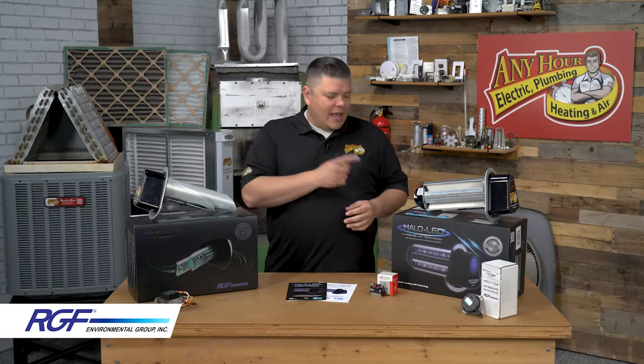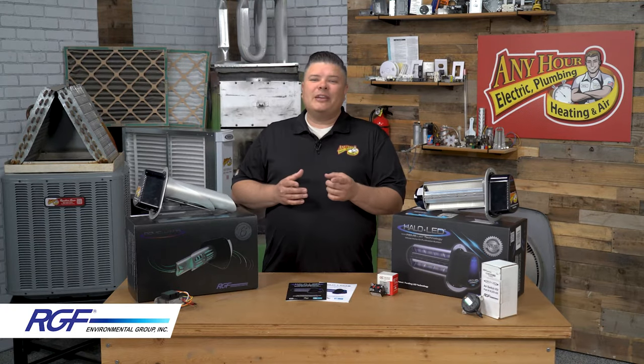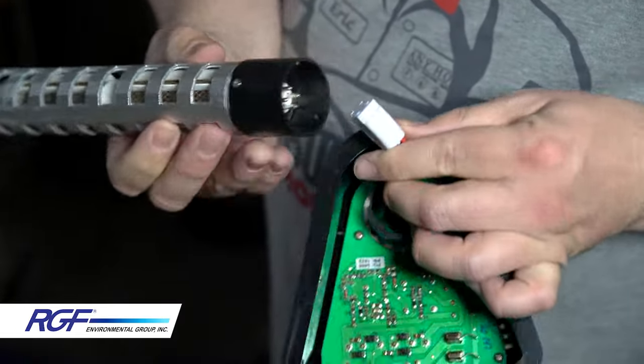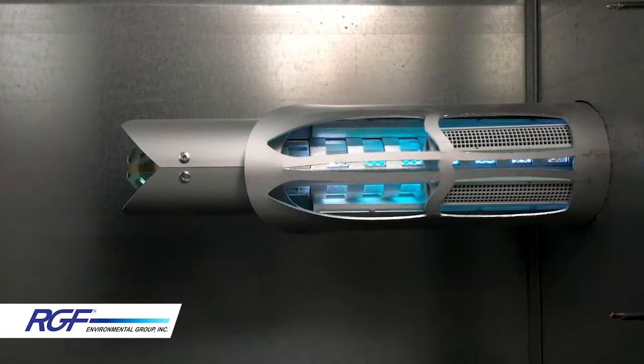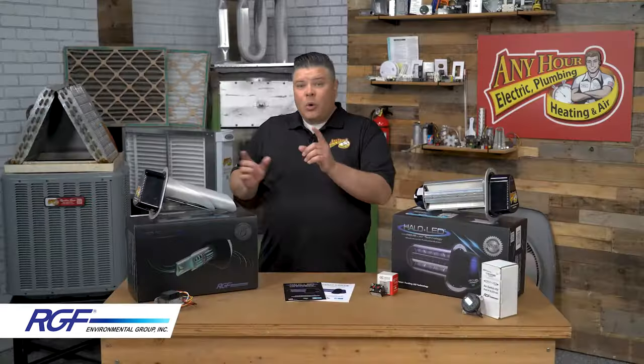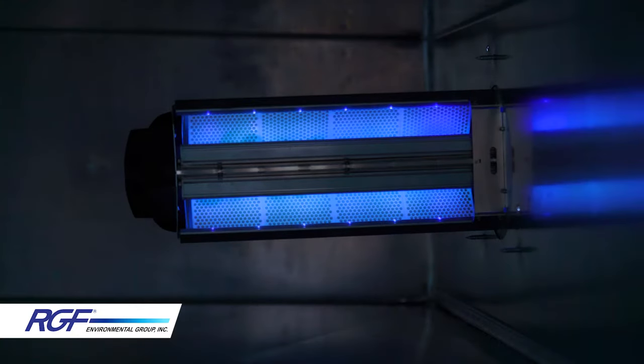The main difference between the Halo LED and the REME HALO is its use of LEDs, so you're going to get improved energy efficiency and longer product life. Instead of changing the cell in the REME HALO every two years, you get five years of protection with the Halo LED. The REME HALO was designed to be on all the time, whereas the Halo LED is the exact opposite — it was designed to cycle on and off in order to get the maximum life out of it.